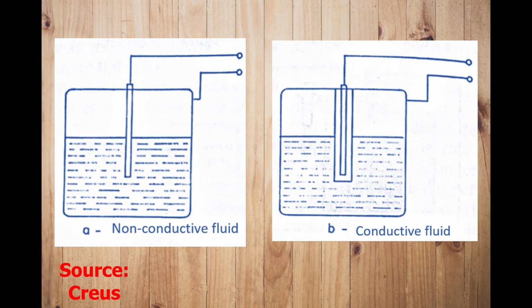The capacitance level sensor measures the capacity of the capacitor formed by the electrode immersed in the liquid and the walls of the tank. The capacity is linearly dependent on the liquid level. In non-conductive fluids, normal electrodes are used, and the total system capacity is made up of the liquid capacity, the upper gas capacity, and the upper connections. In conductive fluids with a minimum conductivity of 100 microsiemens, the electrode is usually insulated with Teflon, with the additional capacities between the insulating material and the electrode intervening in the liquid and gas zone.